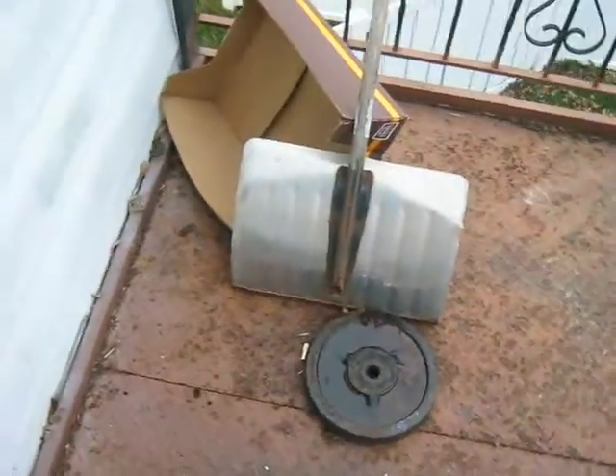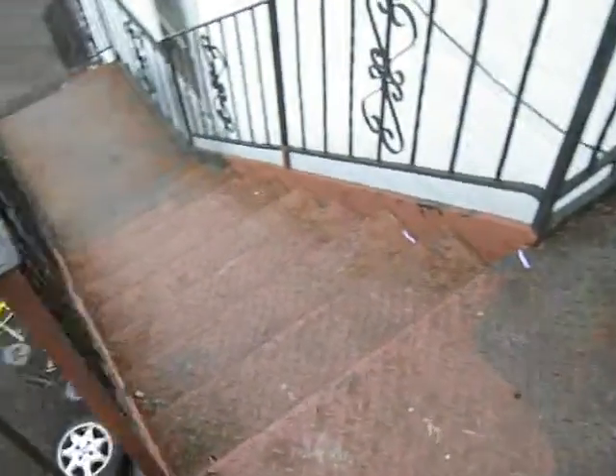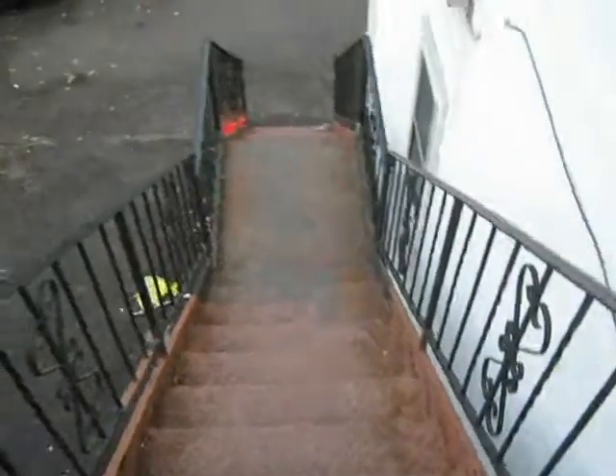The authority having jurisdiction shall accept by load test or other evidence of strength. We cannot provide either one. We cannot provide a load test. We cannot provide other evidence of strength. The fire escape needs major work done to it in order for it to then be load tested.